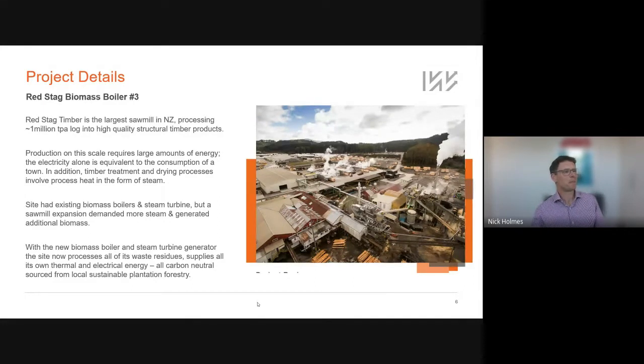A mill of this size has a huge demand for power, both electric to drive all the motors and drives around the plant, as well as the thermal load that goes into the kilns, as steam to heat up the air to dry the timber. So I guess they have the perfect scenario. They generate a waste product, the sawdust and the shavings, and they have a huge thermal demand. And typically they do balance out.